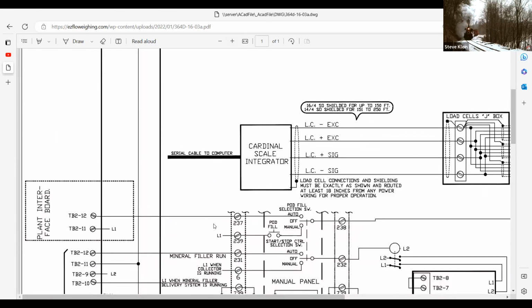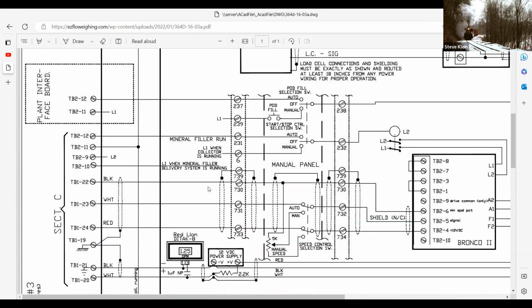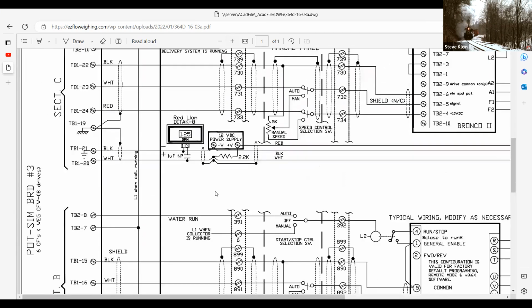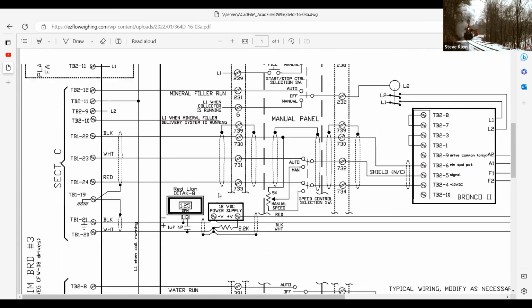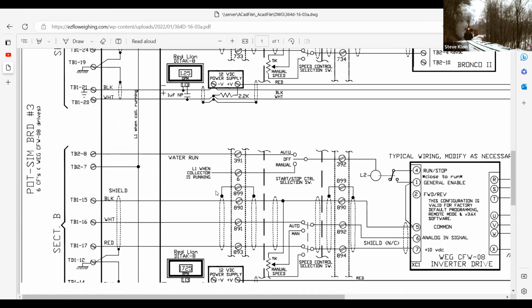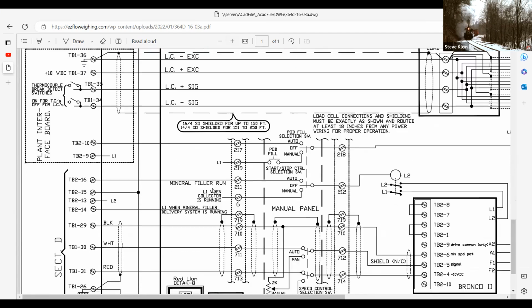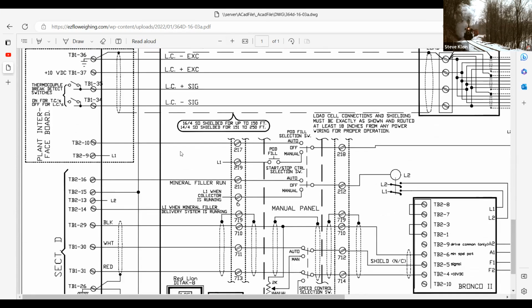Clarence, you're right about that being powered through that relay. But if you go down here to terminal board 2-8, terminal board 2-7, that's probably your run signal. And terminal board 2-3, 2-1, and 2-9 would be the forward-reverse part of the circuit. There are standard jumpers in there so nobody can come in and change it from going forward. And anytime you give it power on your L1 and L2, it has permission to run.